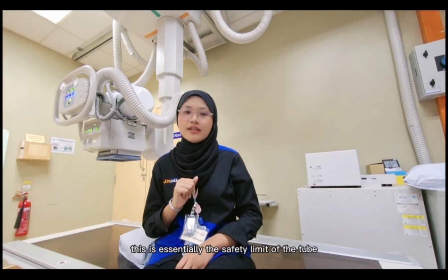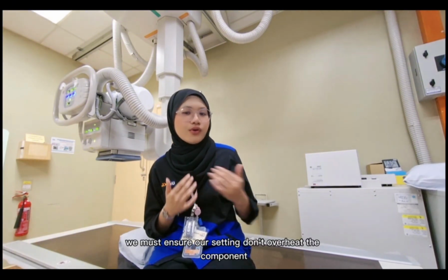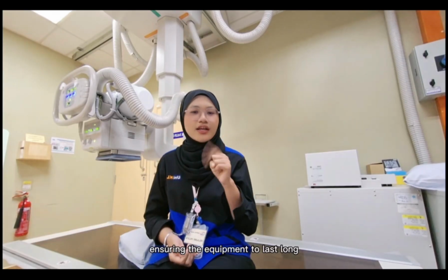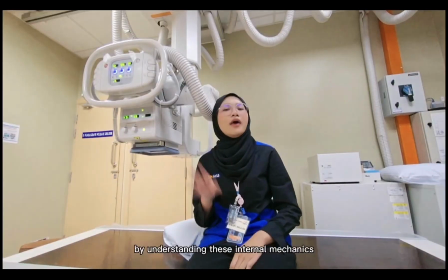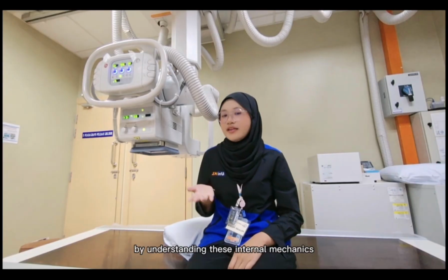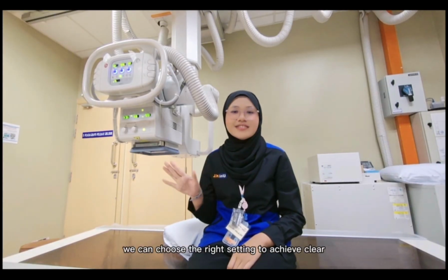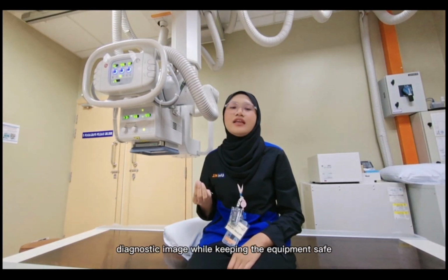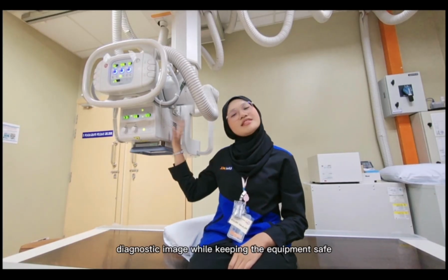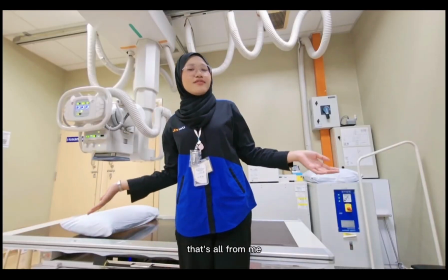This is essentially the safety limit of the tube. We must ensure our settings don't overheat the component, ensuring the equipment lasts long. By understanding these internal mechanics, we can choose the right settings to achieve clear diagnostic images while keeping the equipment safe. That's all from me.